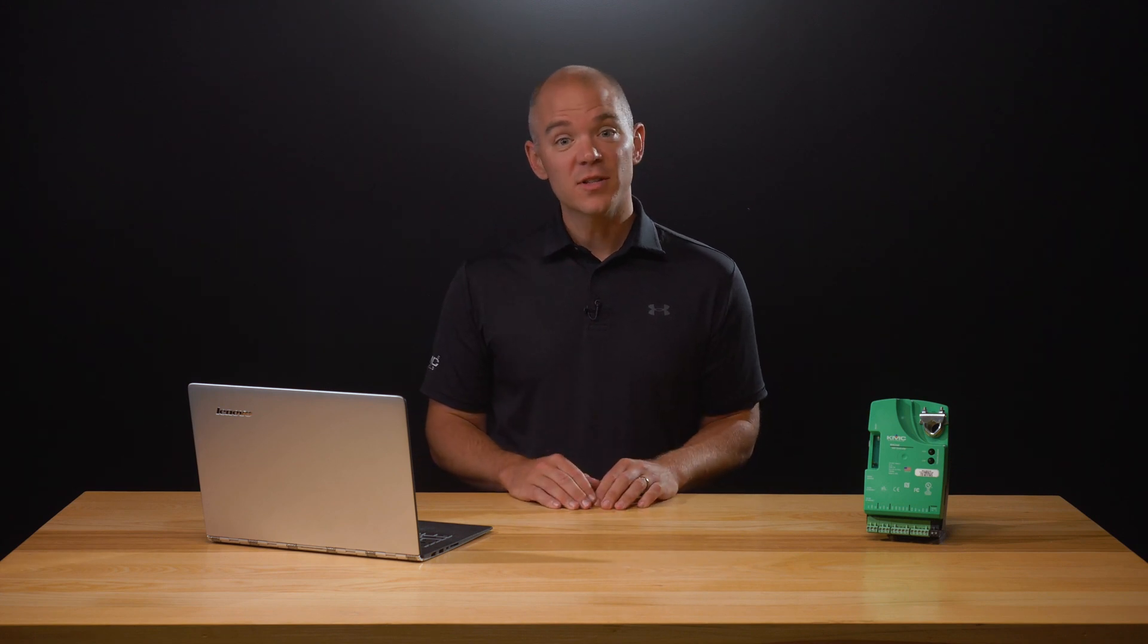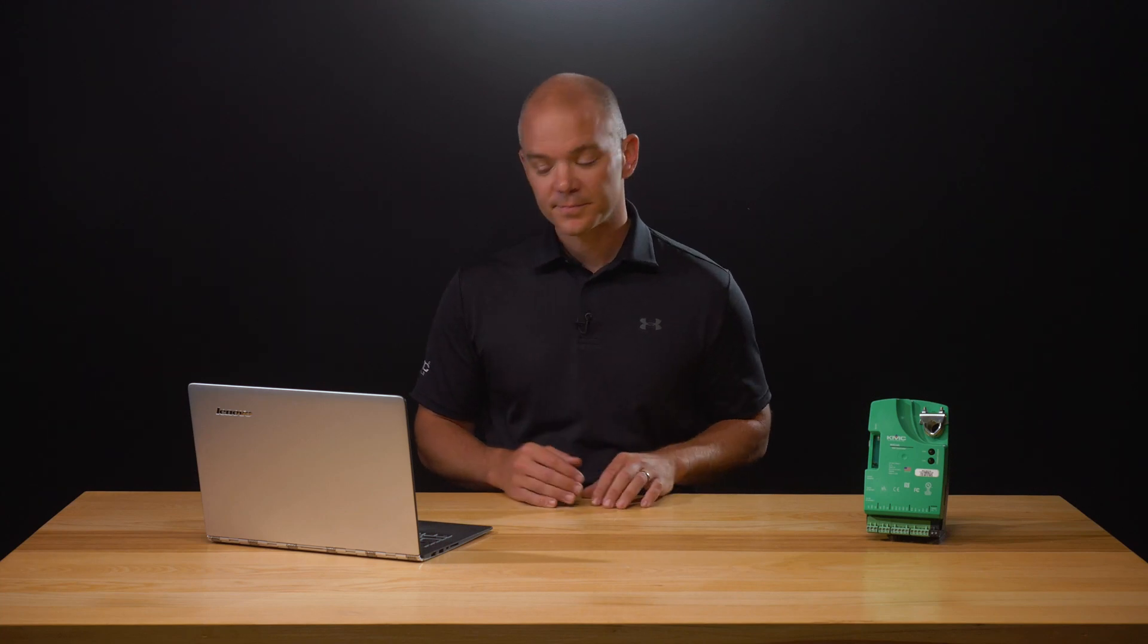Now, we're going to move on to writing code using the time on and time off keywords while making a basic comparison. This will allow us to control a point based on how long an input or an output has been on or off. If time on B01 is greater than 20 seconds, then A07 equals 25. This statement says if binary output 1 is on for more than 20 seconds, then the analog output will change to a value of 25.